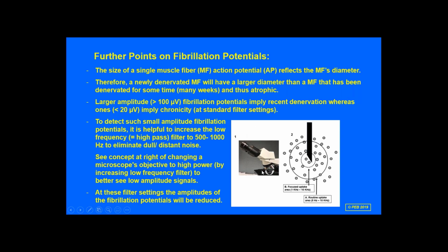it to a microscope. And here we have a low power objective and a high power objective. So if we can change it and sweep and bring the high power down here, we can reduce the recording area of the electrode, and it doesn't matter monopolar or concentric here, to a smaller defined area so we see what's going on at the tip here. So we give up area that we're recording from, but we're gaining the ability to see the detail of the microenvironment right at the electrode tip.